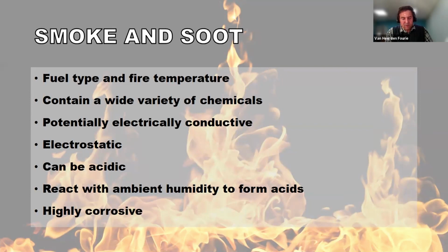Smoke and the resulting soot from the fire can cause a lot of damage in the hospital. The chemical composition of soot is mainly determined by factors like fuel type and the fire temperature, which is also influenced by the presence of oxygen, and some other factors. In severe cases of soot contamination, the soot can cause short circuits on printed circuit boards and electrical contacts.